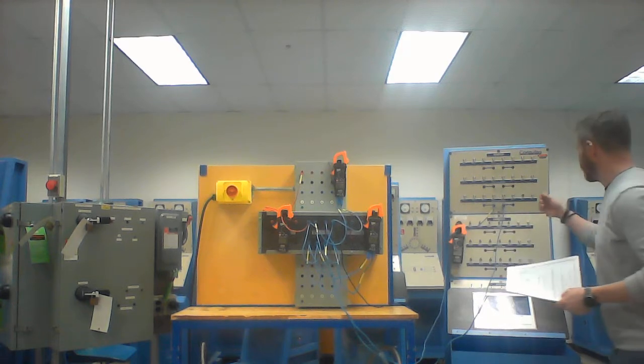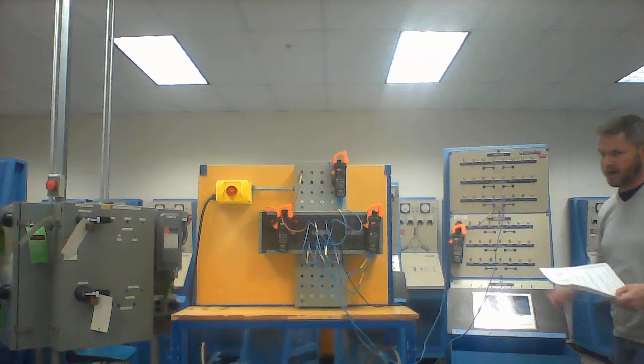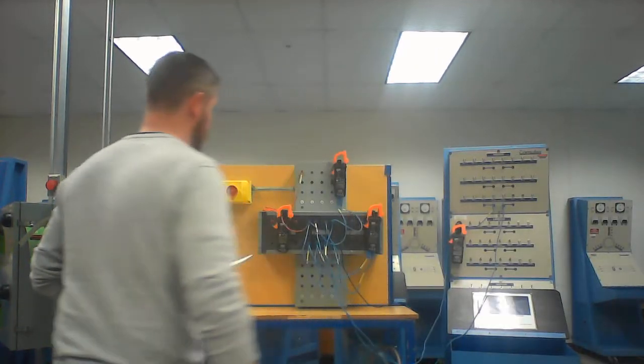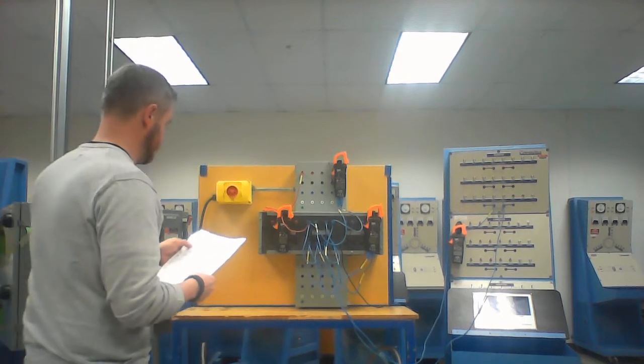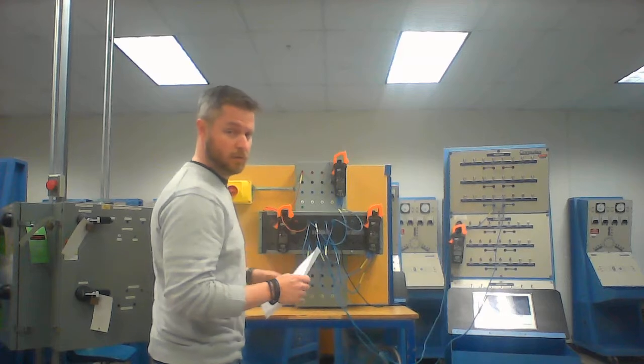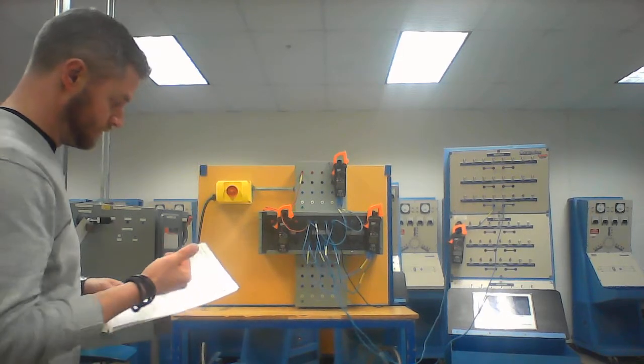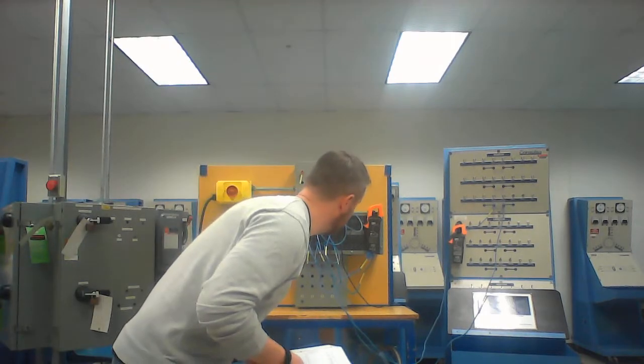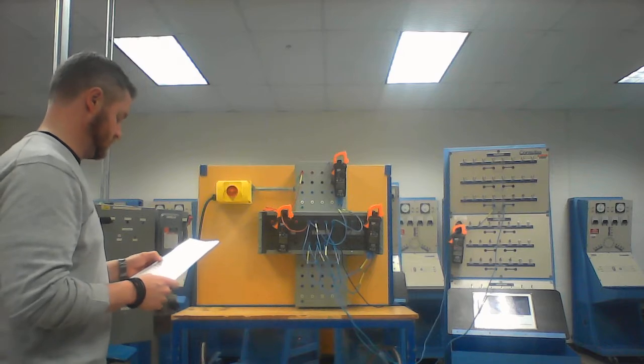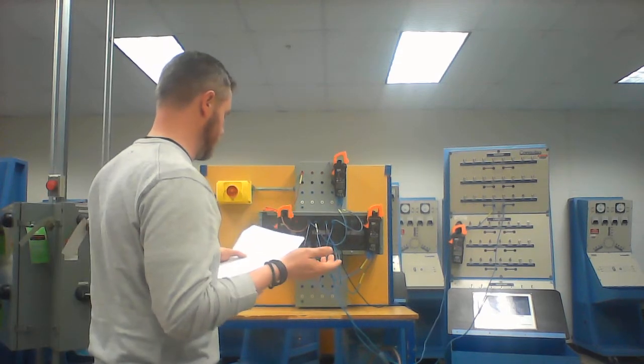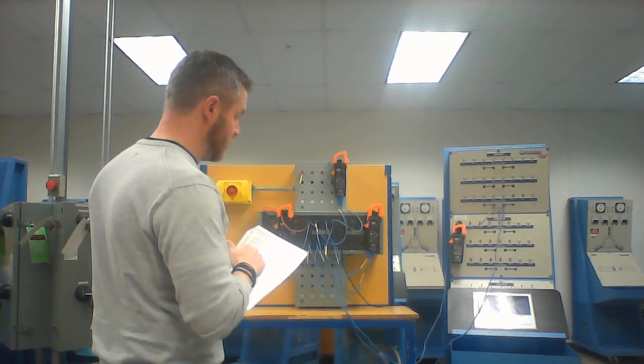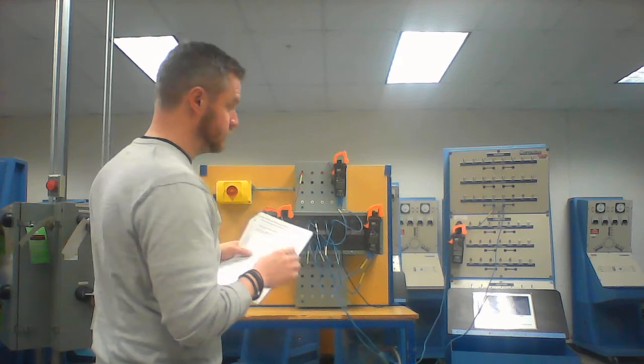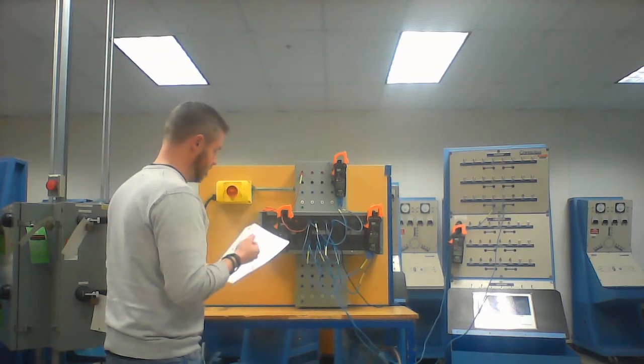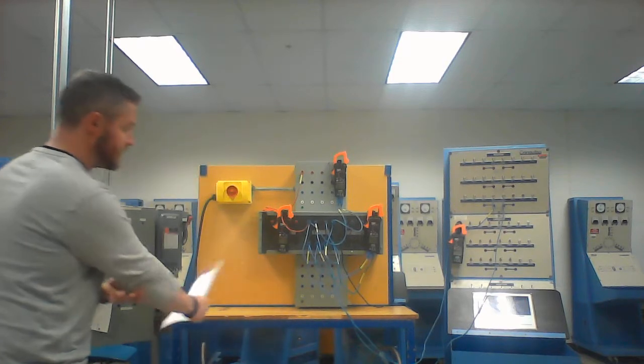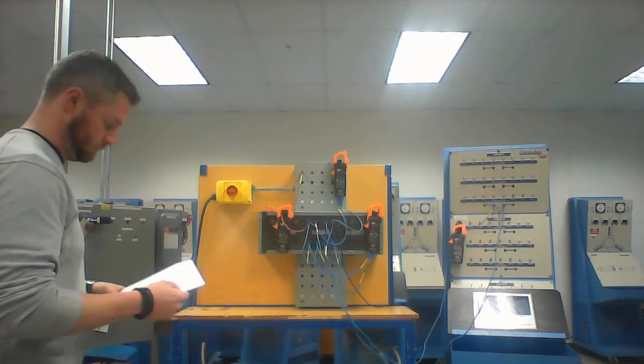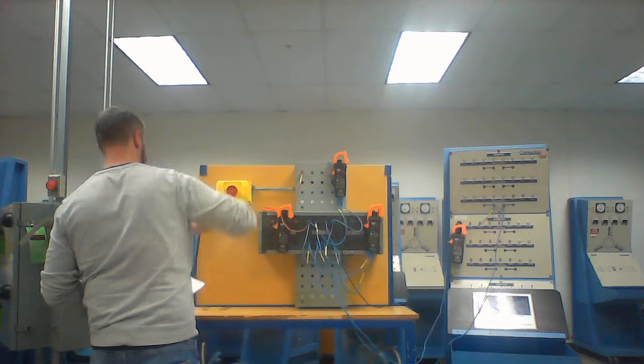Now I want to do 73 ohms. I get a 73 ohm resistor by putting on a 110 and a 220. So at 73 ohms, my primary voltage, 202.1. Secondary voltage, 118.8. Voltage ratios we'll do later. 100 milliamps for your excitation. Measured secondary current, 1.55. And your measured primary current, 1.03. Perfect. Turn that off.